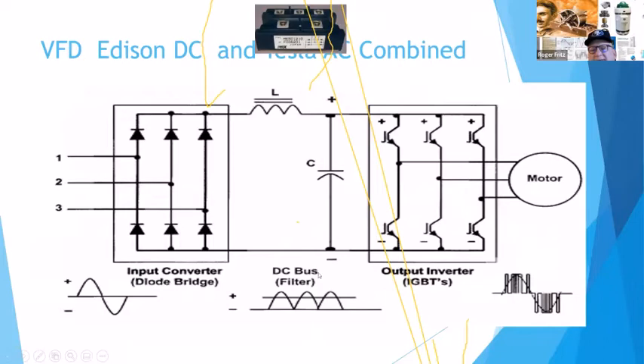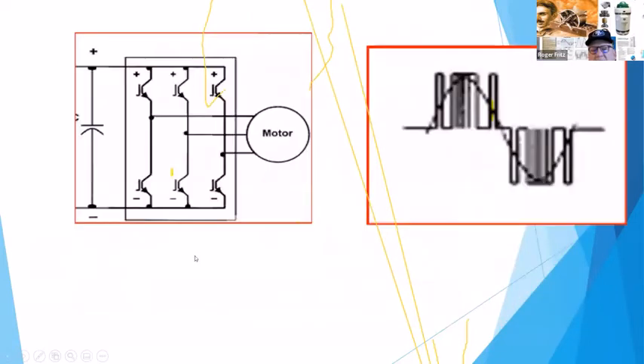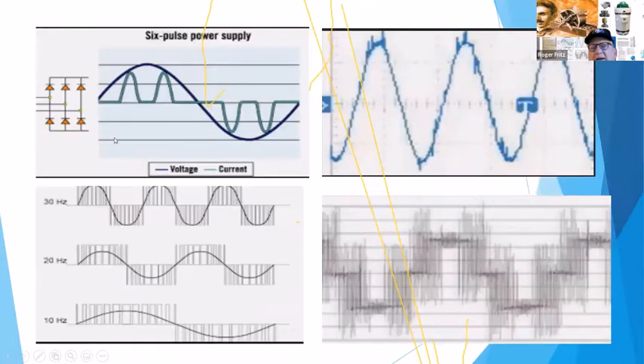So as we're feeding this capacitor to build this, it doesn't draw the power linearly. It's called nonlinear power. Well, what happens is when this pulses like this, we're creating pulses twice instead of just 60 cycle power out there. All of a sudden, we're seeing 120 hertz current forms, which then inherently go back and start affecting the actual voltage waveform. So from that voltage waveform, it's very important to understand that we've got to keep this below the threshold of what the winding is originally designed for.